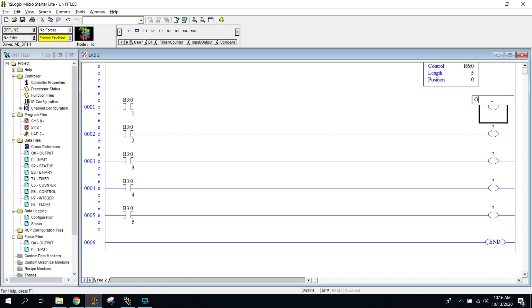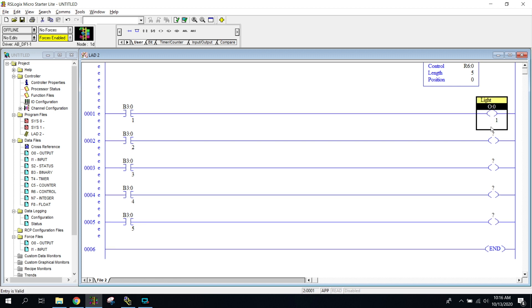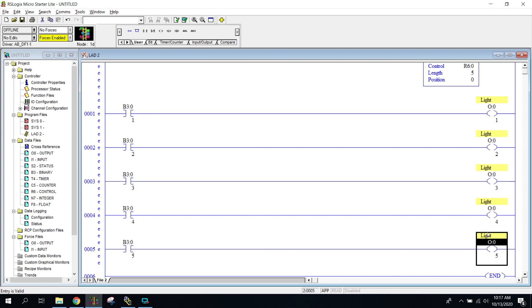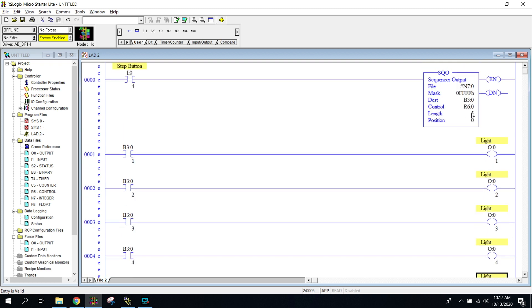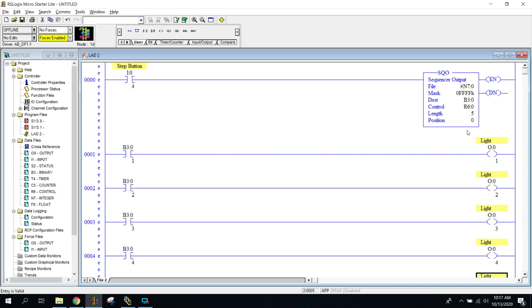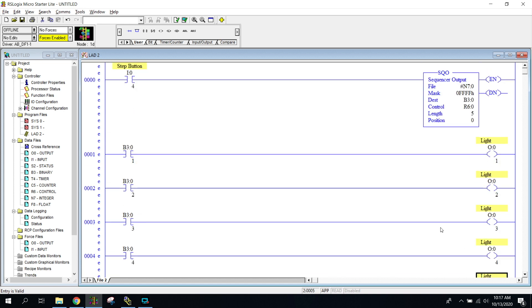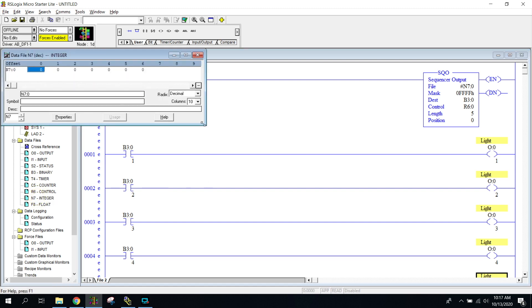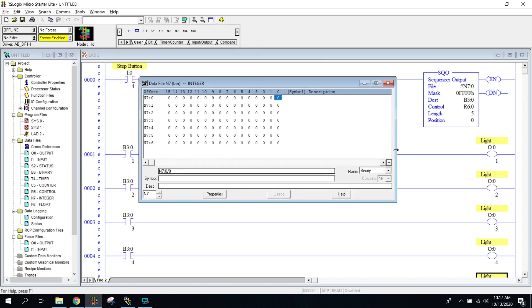We've pretty much set up our program now — every different step is going to be turning on a different light. Right now we don't have our N7 file set up, so let's look at that. I'm going to go over here to my Radix and switch to binary. When I do this, I suddenly have a bunch of different files — each one is linked to a different N7:1, :2, :3, and so on, and each one has 16 bits to write, so I can potentially turn on 16 different bits.